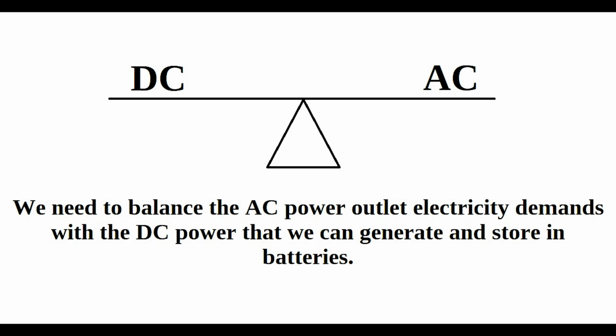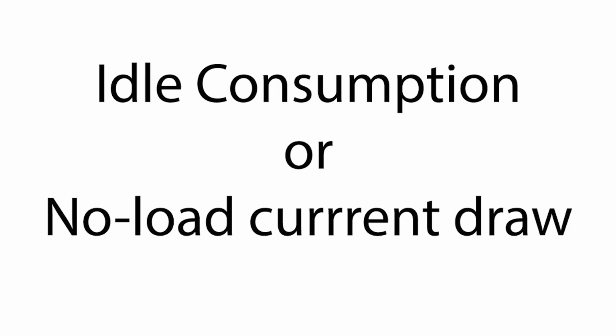However, something important to keep in mind is, if you have your inverter turned on, however nothing is actually utilizing any of the AC power the inverter is creating, the inverter will still be taxing your battery or batteries of some of their stored power. Again, it's called an idle consumption load, or sometimes a no-load current draw, which will effectively, if maybe slowly, drain your batteries whilst the inverter is not actually supplying any AC electricity to anything. The larger the wattage rating of the inverter, the higher the drain it will put on the batteries in the way of idle consumption or no-load current draw. Again, regardless of whether it is actually being used to supply AC power or not, as long as it's turned on, it's using some DC battery electricity. So keep that in mind. Be sure to turn the inverter off when not in use.